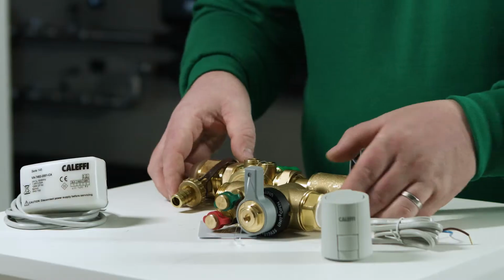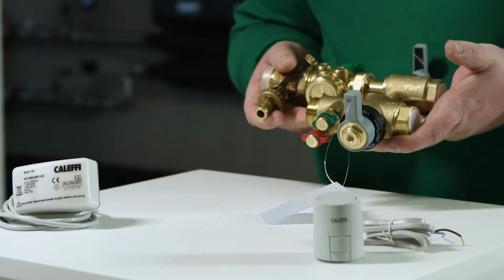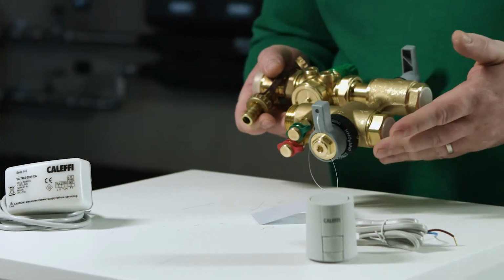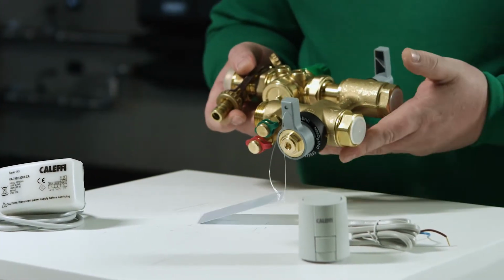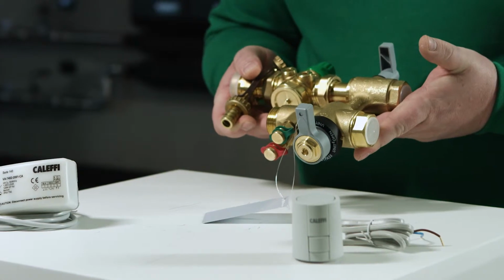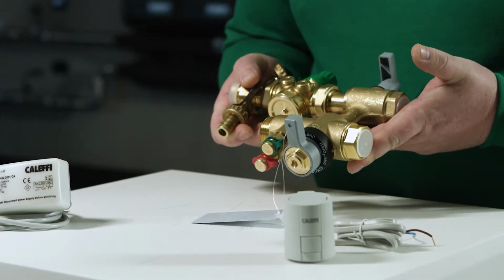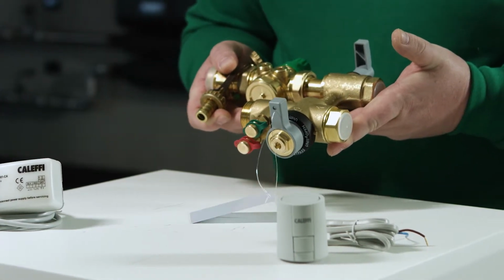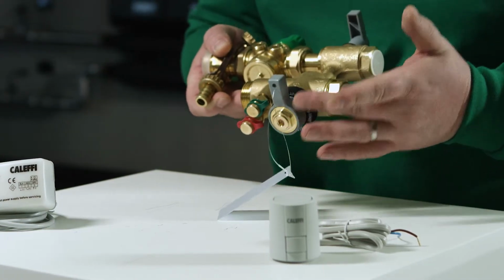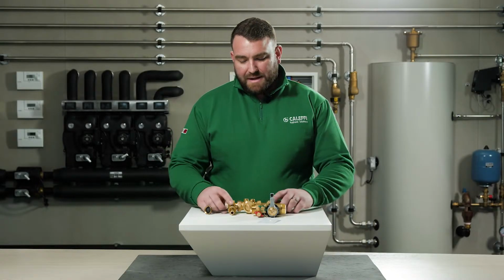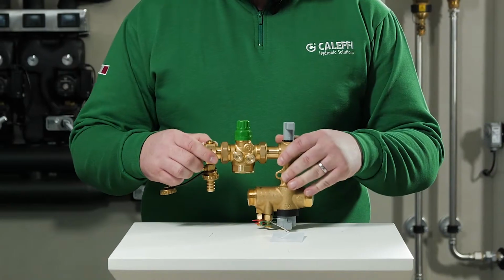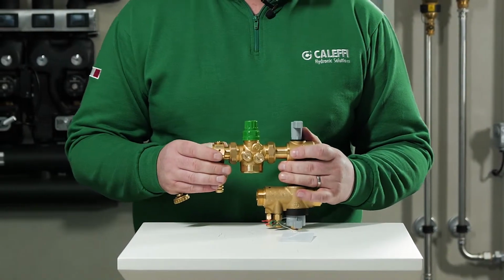We will now talk about the functions of the 3-way valves. We can now bypass the terminal unit for initial flushing or to maintain circulation during the maintenance, complete shut-off for maintenance, or standard function of the unit. Inside inlet shut-off valves, there is a strainer for the unit protection. Using the Flowmatic PICV, it is possible to set the maximum flow rate required for the terminal unit.